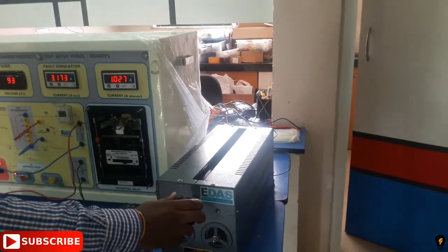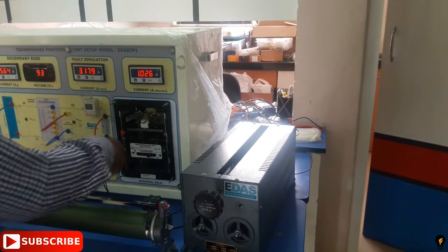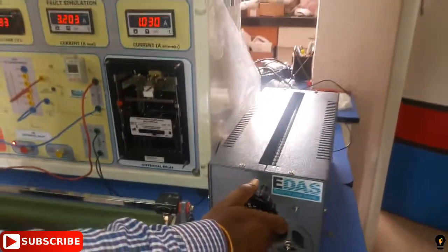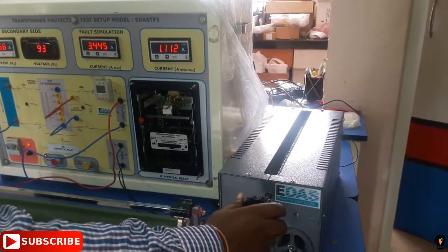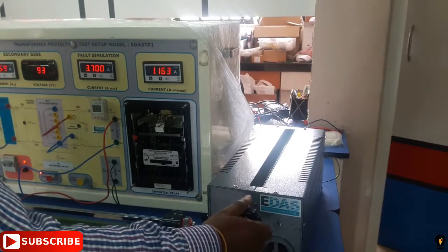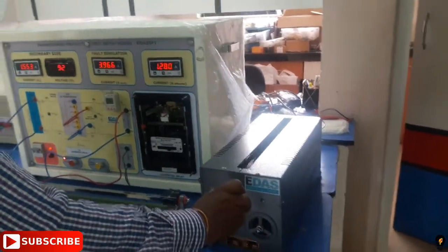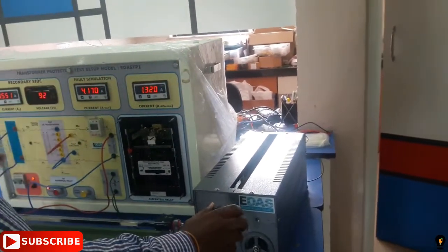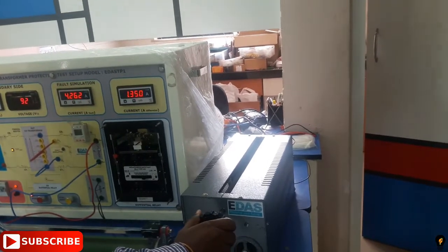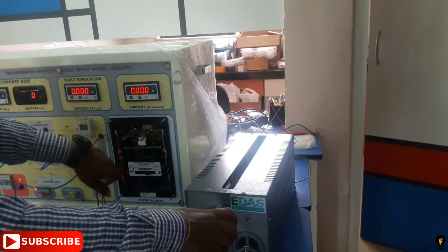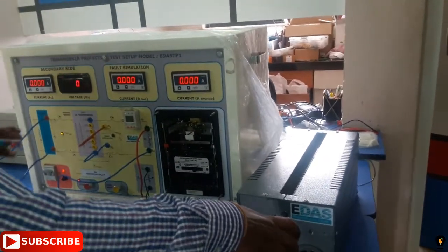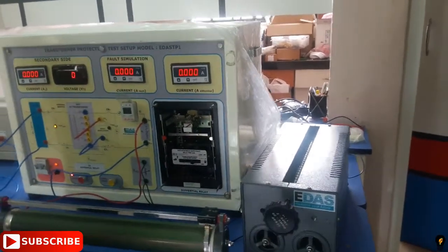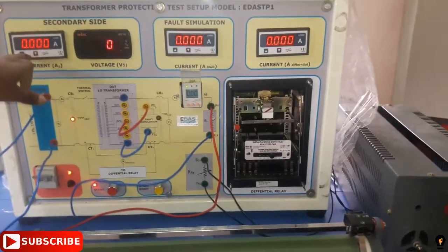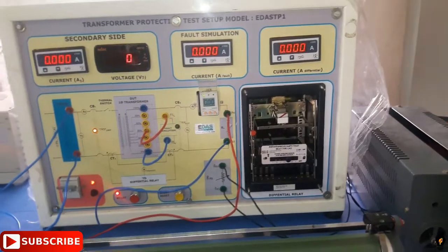Now extend further in such a way that the differential current exceeds 1.5 ampere, because we have set the differential relay at 0.3, which is 30% of the differential current. At this stage, the differential relay picks up and the DUT will be isolated from the source unit. So we have to exceed the differential current of 1.5 ampere. Here you can see the differential relay has tripped and our source unit is isolated from the main source. Okay, so here you can see zero current at the secondary side.